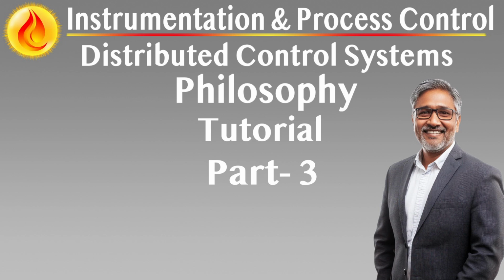Overrides, maintenance, and diagnostics. Controlled maintenance override functions. Individual detector inputs can be overridden for maintenance under a dual authority protocol. Overrides are initiated via secure workstation interface, enabled through hardwired maintenance toggle switches (MOAS), and flagged via alerts and HMI indication. No output overrides permitted. Outputs tied to suppression systems, shutdown actions, or life safety responses cannot be overridden. Any attempt or system fault forces a visible alarm on the console and mimic panel.